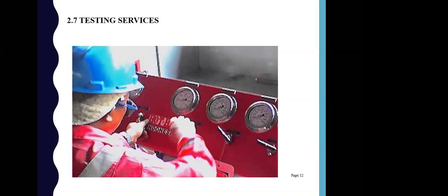So the test could be in-house by the contractor himself, or with a specialist third party, but all tests should be certified by the supervision engineers, witnessed, and should have a test report attached. We should have a log for the tests conducted, using this as part of the handing over and completion certificates for the building.